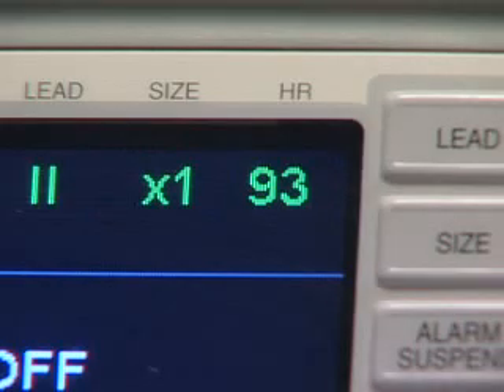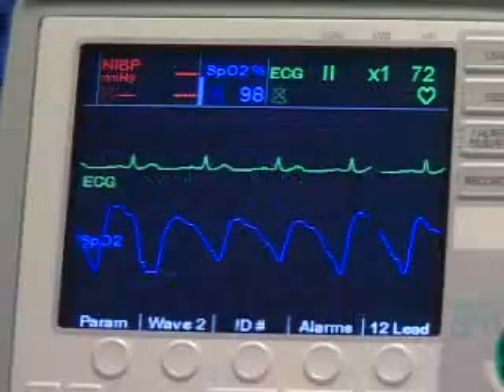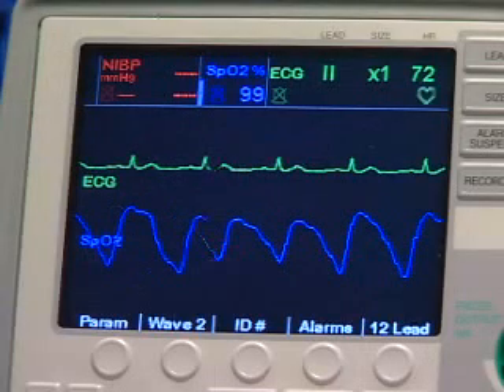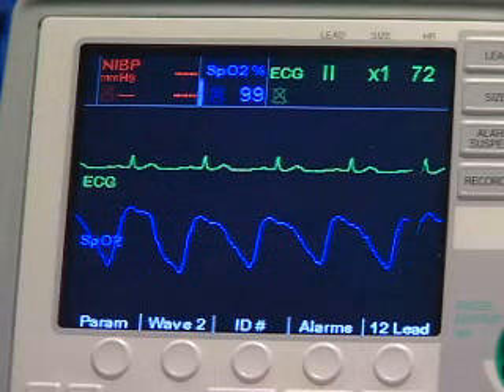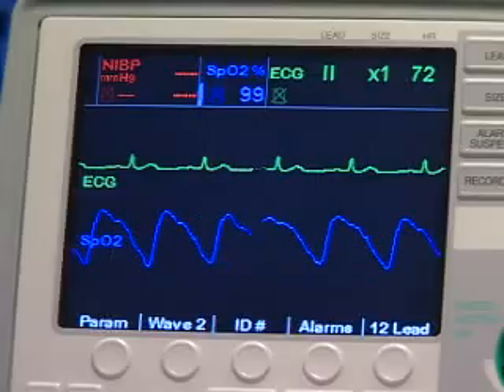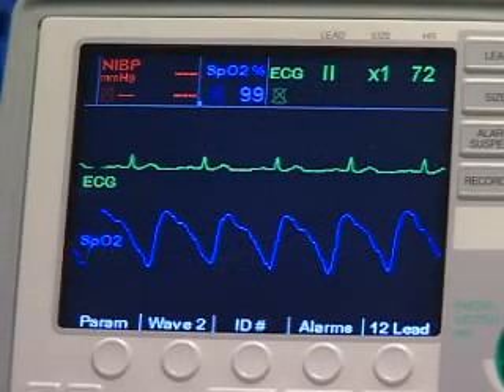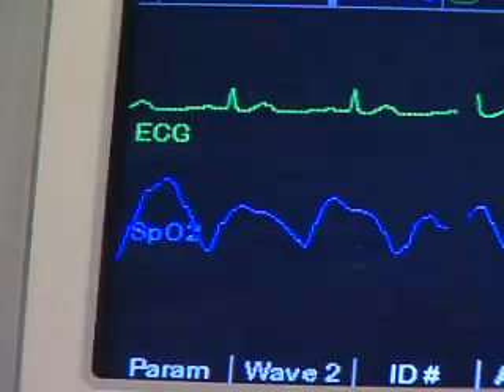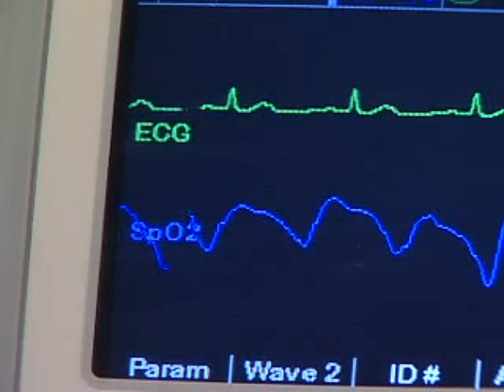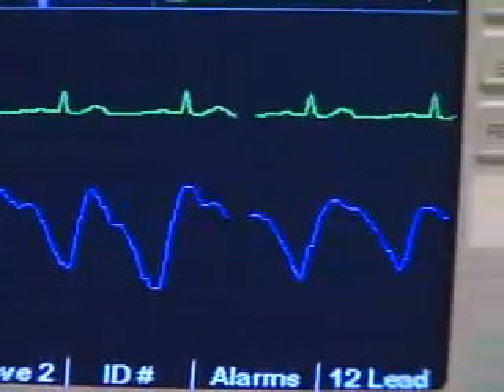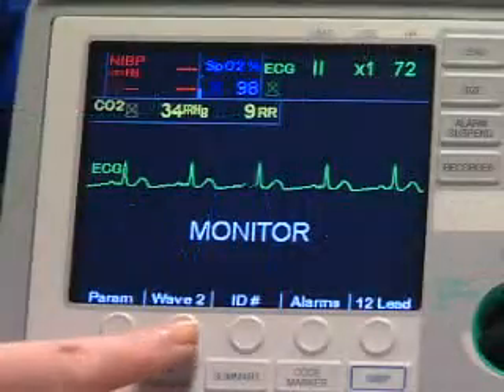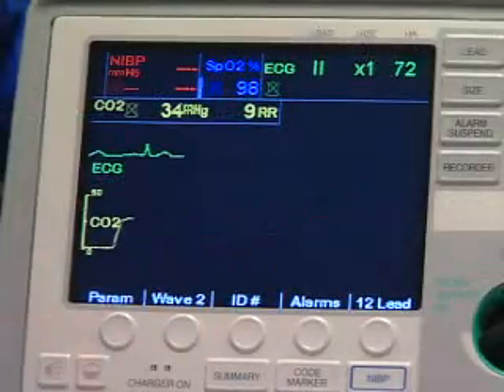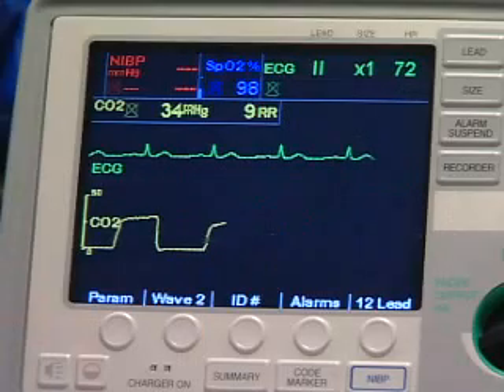If ECG leads are not attached, your patient's pulse rate measured by the SpO2 sensor will be displayed as the heart rate in the ECG field, and the heart symbol does not flash. The E-Series can display one or two waveforms in monitor, defib, or AED mode as long as it is not charging or ECG analysis is not in progress. With SpO2, the unit can display the pleth waveform below the ECG trace for a visual indicator. From the monitoring menu, press the Wave 2 soft key to cycle the display on the E-Series.